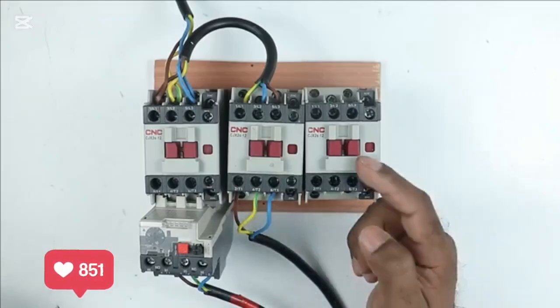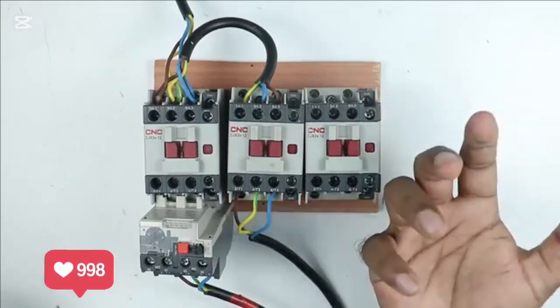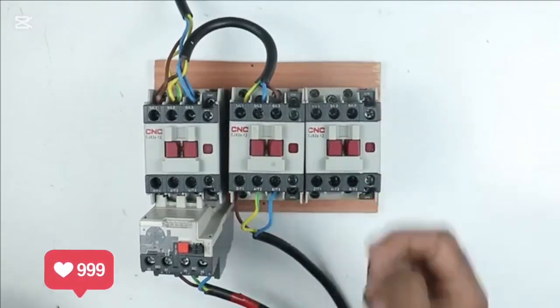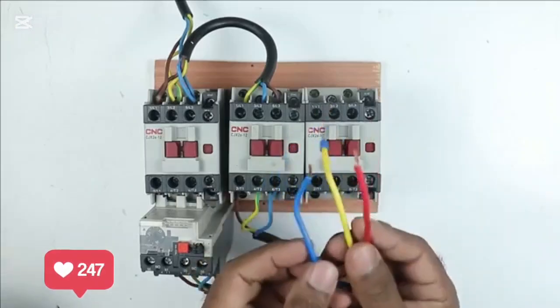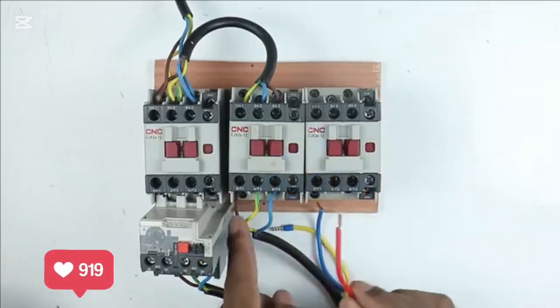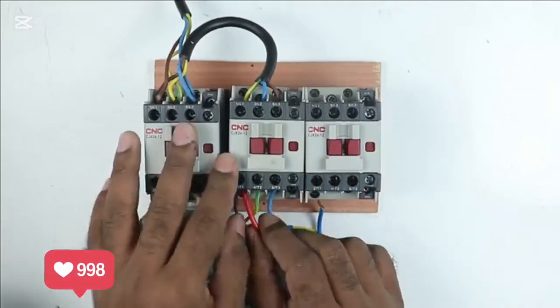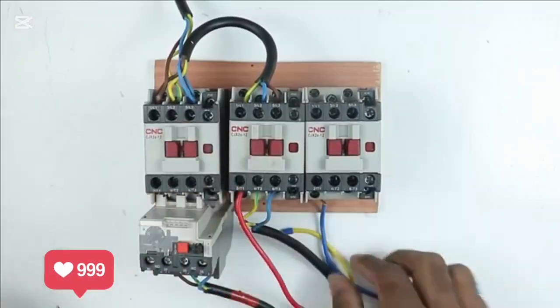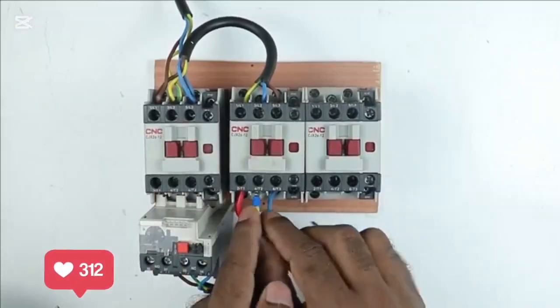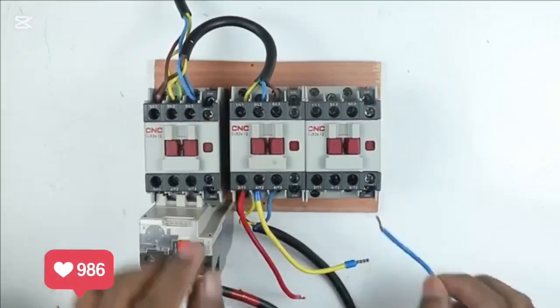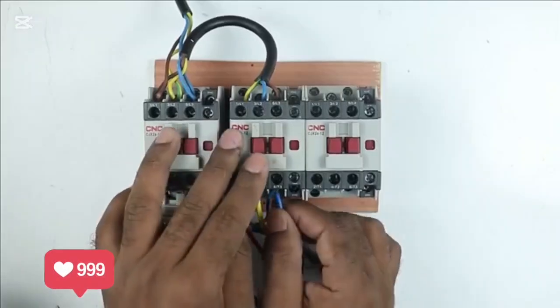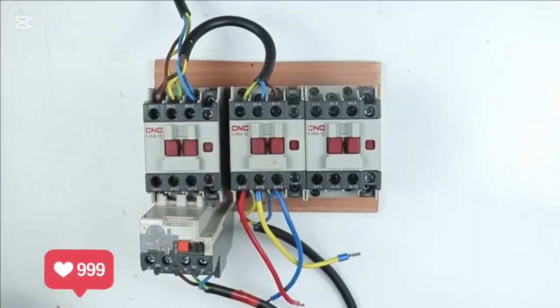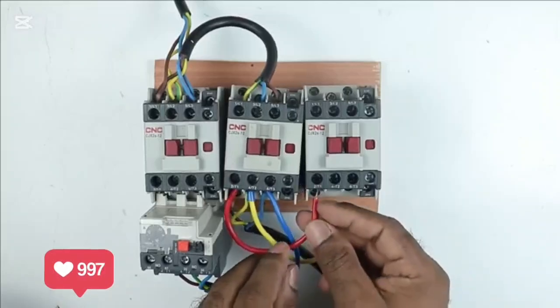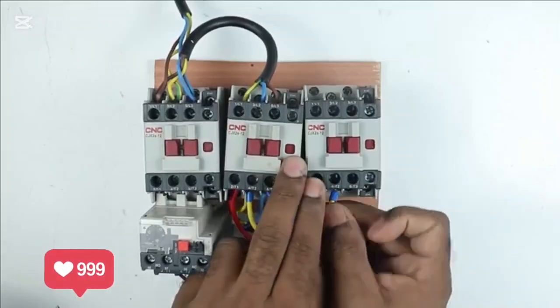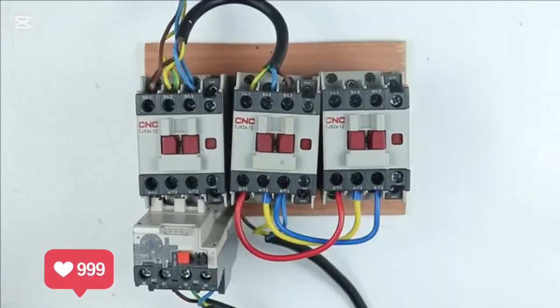to do with this another contactor here, you have to make star connection. For connection in this star contactor, simply take 3 wires. Take these 3 wires and connect with these 3. If we even interchange here, there won't be any difference. What I am doing is, with R phase, connect R wire, with Y phase, yellow wire, and with B phase, connect blue wire. As per the sequence, I did the connection. Take other end of wires and connect directly here. You can connect anywhere, it does not matter. Simply I did the connections over here.